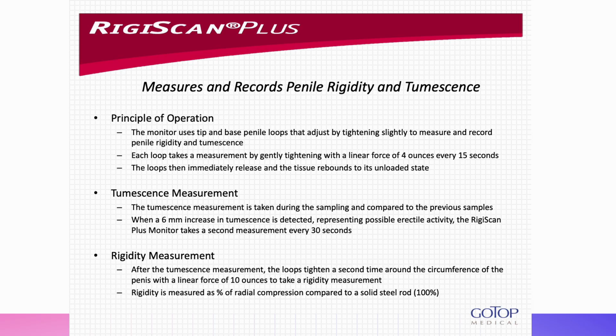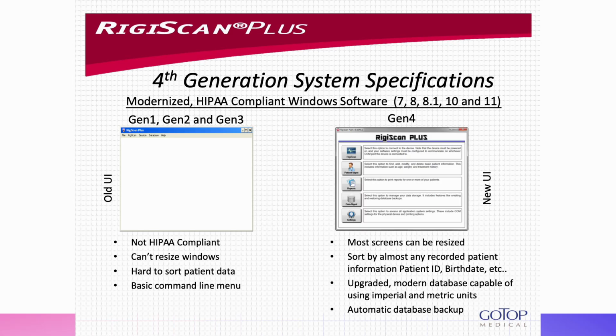How it measures. The device components comprise 2 non-elastic loops that are placed around the base and tip of the penis. Each loop contains a cable that moves freely inside a conduit, tightening slightly at discrete time intervals. The measurement process involves each loop gently contracting every 15 seconds with a linear force of 4 ounces or 114 grams, then immediately releasing, allowing the tissue to rebound to its unloaded state.